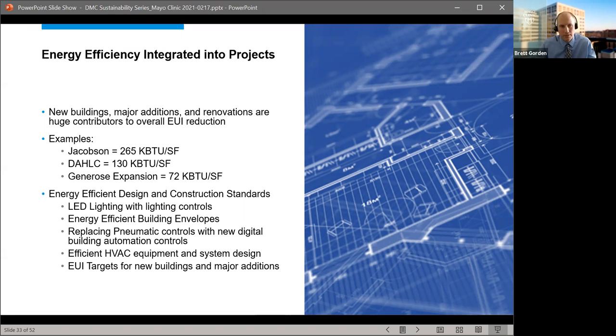We are replacing our boilers in the Franklin Heating Station right now, which is going to increase our efficiency a great deal in that facility. We're going from boilers from the 1950s, about 60-some percent efficient, to brand new boilers at 85+ efficiency. We're continuing to expand our cogeneration capability, which is still gas-fired, but we're creating steam to heat and cool the buildings while also getting additional electrical kilowatts out of that process.